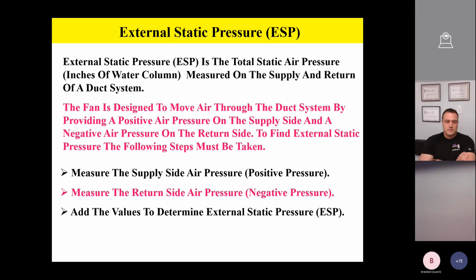So I've found in the field it works best to take one pressure first and then take the other one, because if you do it that way, when you're taking that air pressure by itself, the other side of the gauge, so to speak, is at atmospheric pressure. And so the atmosphere is very stable. It's just Mother Nature. And so if you're referencing your pressures individually to atmospheric pressure, you get a more stable reading. And the result will be you'll have a better overall reading, a more stable and accurate reading.